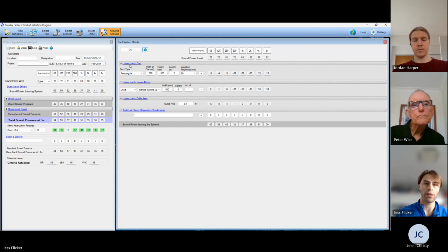So we came in here, and there was a bit of duct connecting to the fan coming through the roof, and we found that with 1 metre of duct with 50 mil lining, it was enough attenuation, even without bends, to get within the standard allowance. So based on that, we justified selecting that fan.